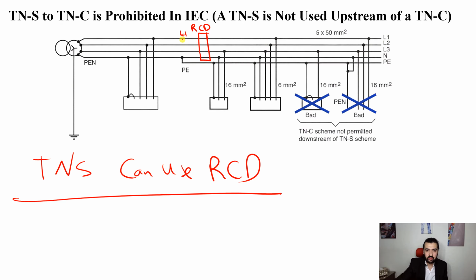We are going to go in depth with catalogs about RCDs. So we have L1, L2, L3, and neutral. And the protective earth is the one that takes fault current, right? Fault current. Great. Now let's look at the system specifically. In normal conditions we will have 3-phase currents IA, IB, IC entering the equipment and then getting back through the neutral. This is my own neutral. PEN is my own neutral.